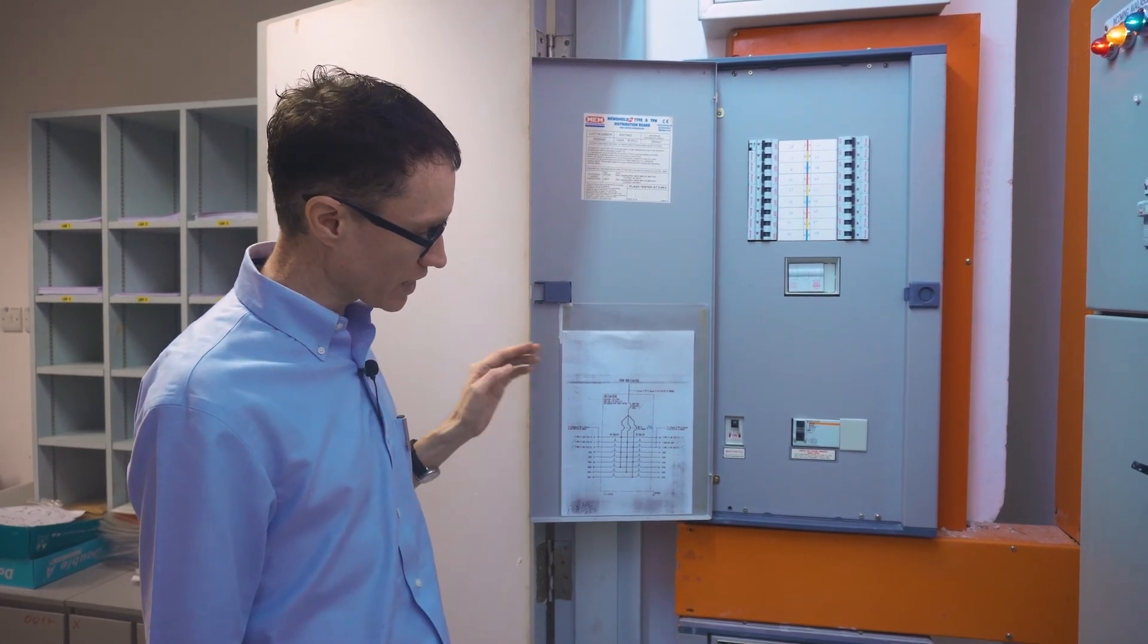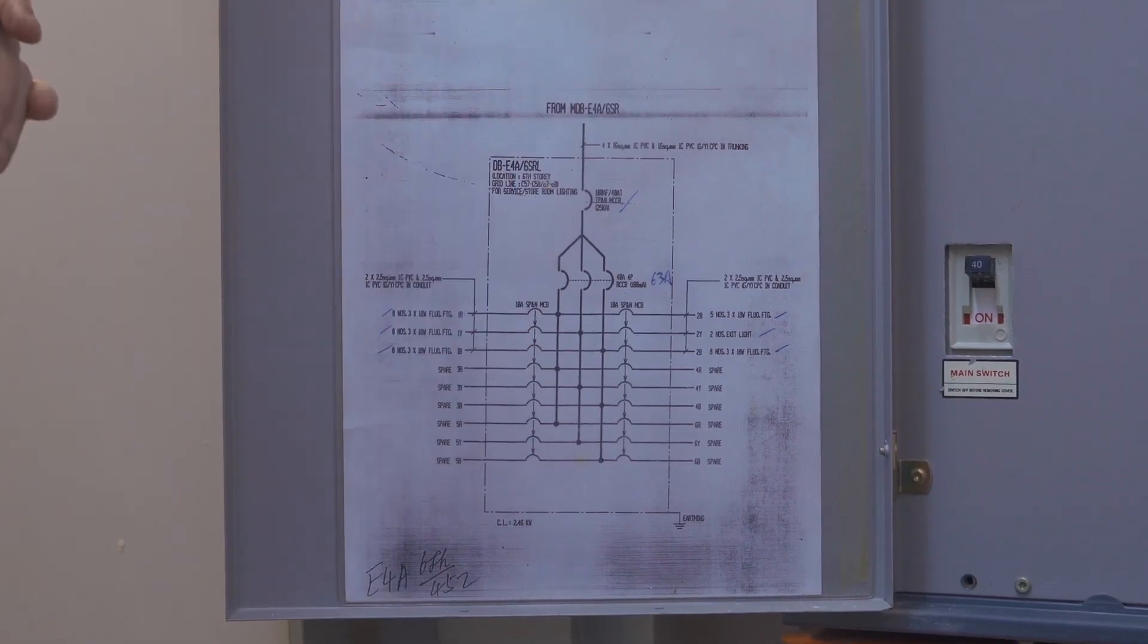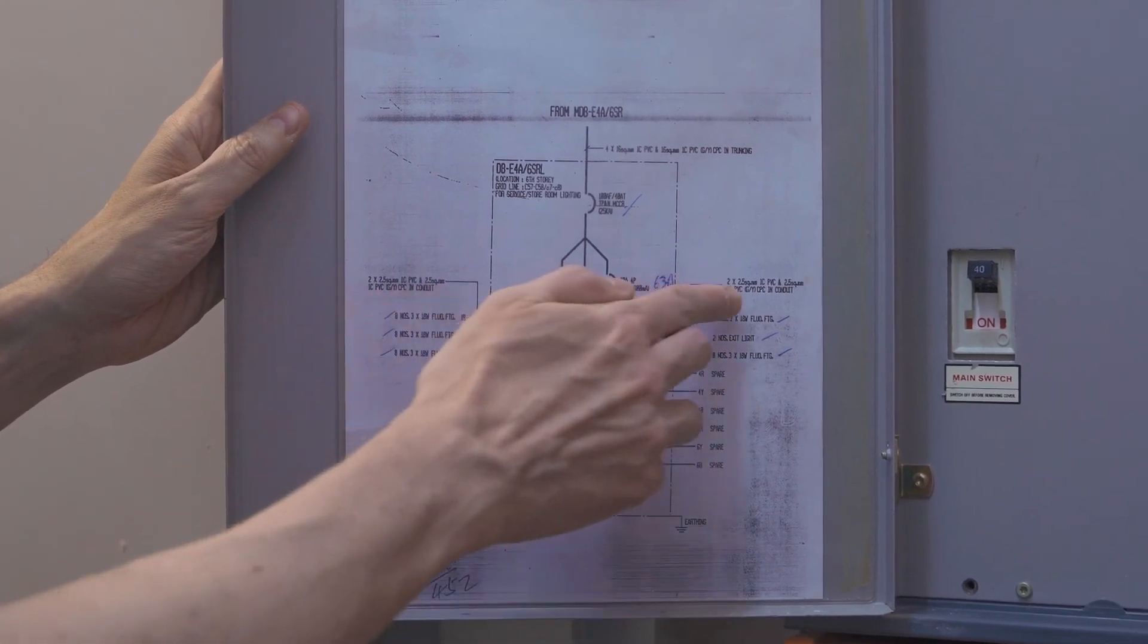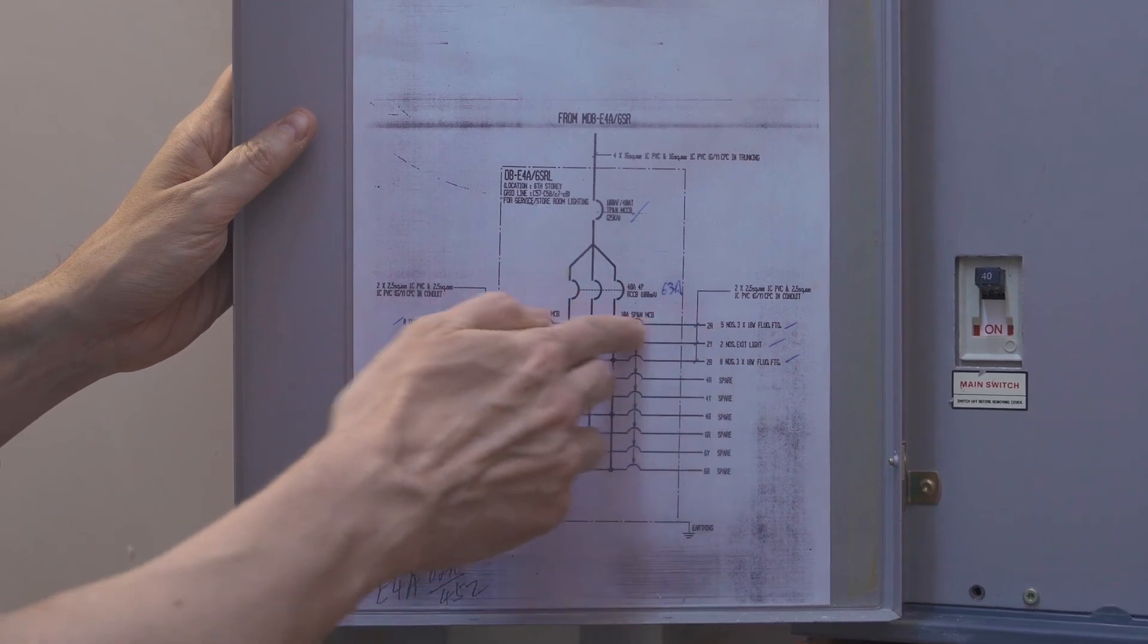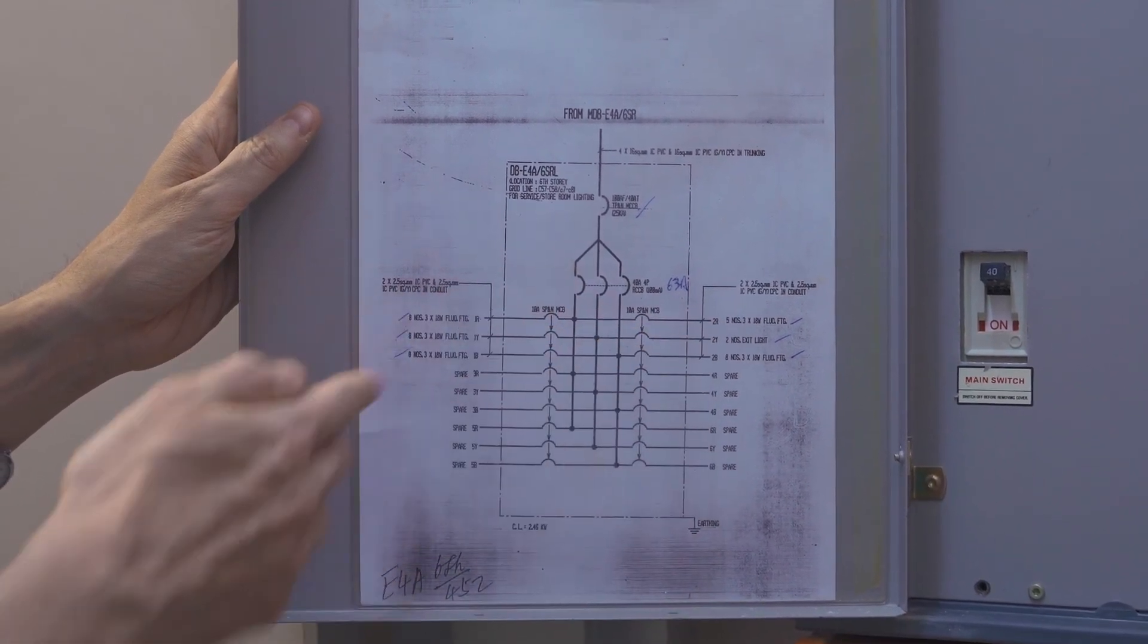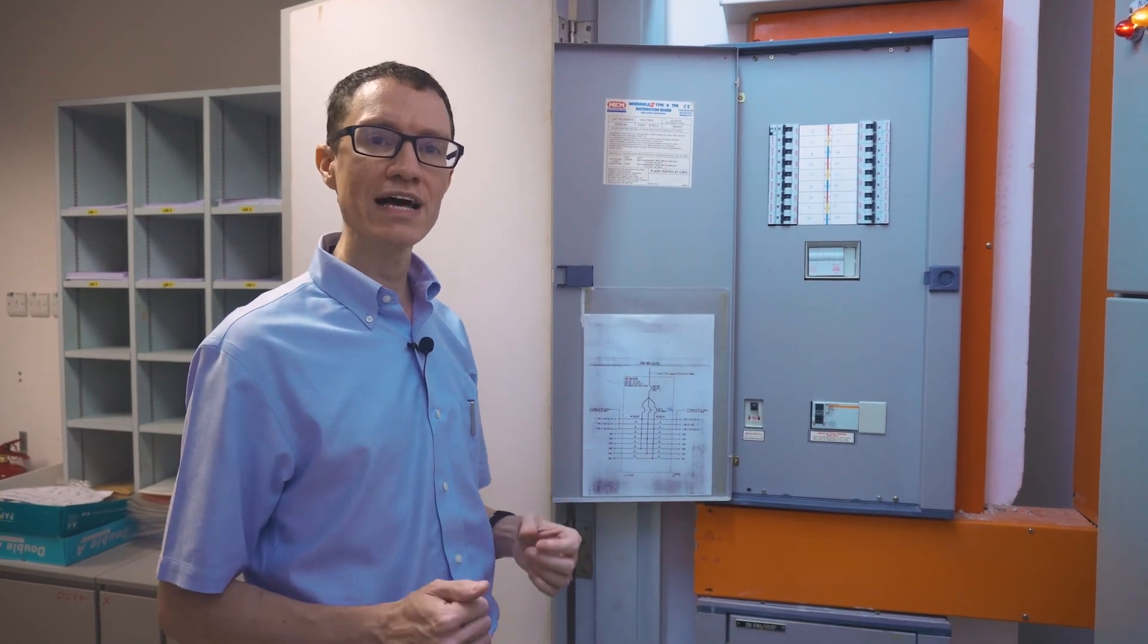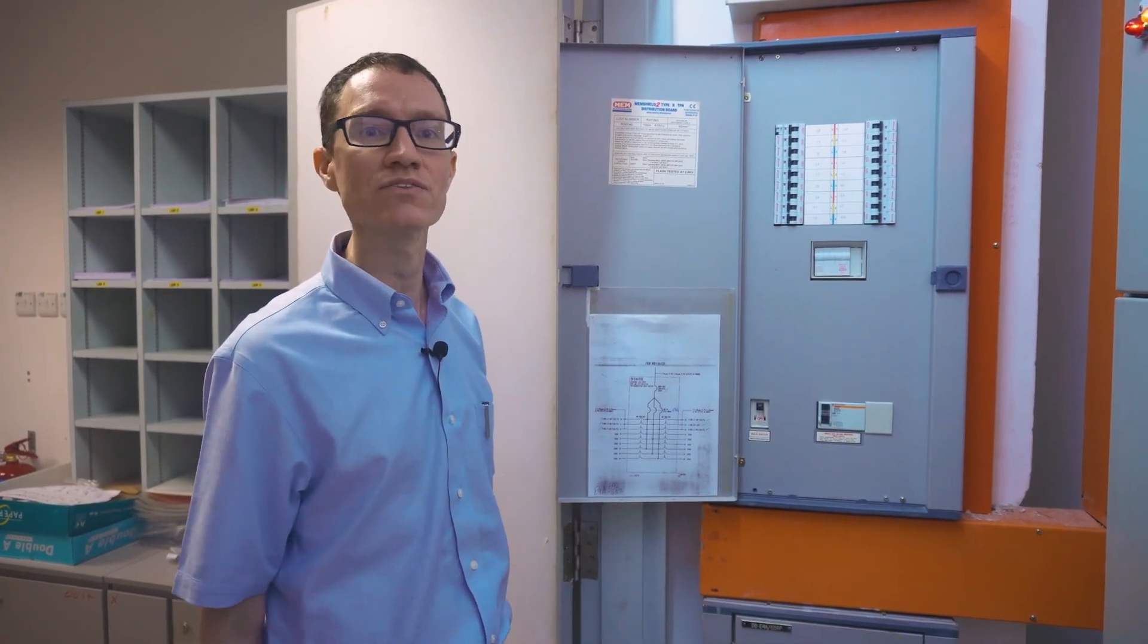This label right here also shows us in a pictorial way how the phases are distributed. So this picture of the box shows that we have three phases coming in here. And then the phases are tapped off in turn. First, the red phase is tapped off, then the yellow phase is tapped off, then the blue phase is tapped off, and then the process repeats. This ensures that power is distributed here in the lab in a sort of even-handed way among the three phases.